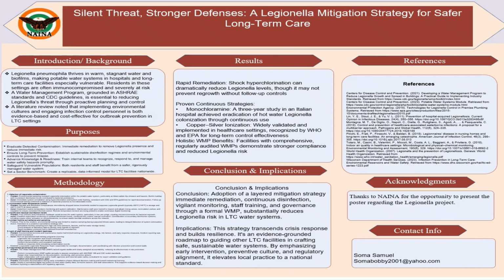Inconsistent water temperature control was another problem, as storage and distribution temperatures intermittently dropped below the threshold needed to suppress Legionella growth, typically more than 60 degrees Centigrade or 140 degrees Fahrenheit in storage, especially at the distal outlets.